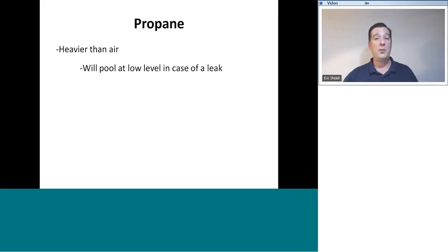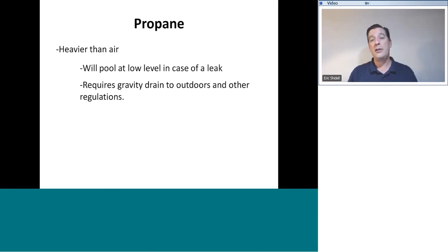And if you're working with a boiler, which is low to the ground, or water heater, which has a burner and ignition source low to the ground, that can create an explosion hazard pretty easily. As a result, codes require there to be a gravity drain to the outdoors, and some other regulations regarding propane installations to promote the safety of this fuel gas.